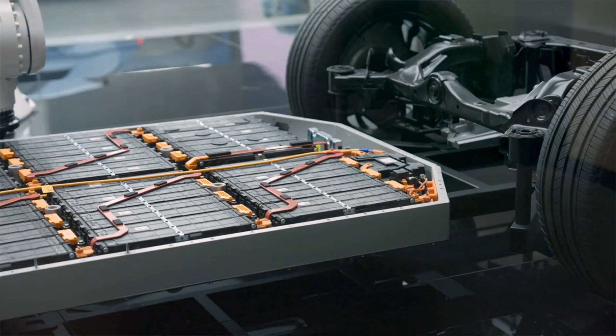The electrolytes used within the batteries vary between manufacturers, but in general they are corrosive, flammable, dangerous, and toxic. In most cases, after manufacturing, the chemicals will not leak from the batteries without a thermal runaway event occurring. So typically, if a battery is damaged to this point, the greater concern is thermal runaway versus chemical hazards. Those are the top three hazards to look out for, but there are a couple more I'd like to share.